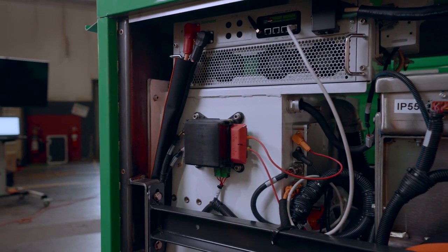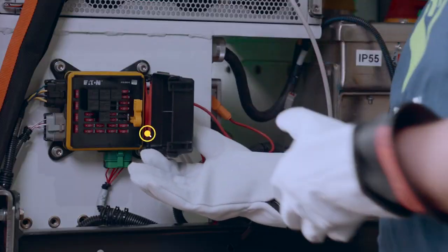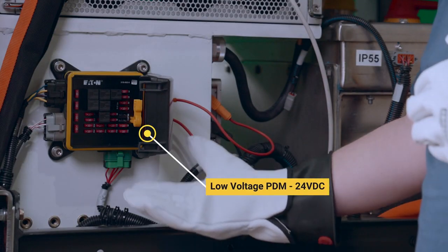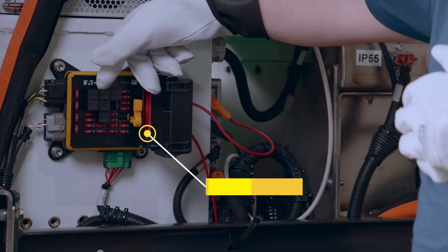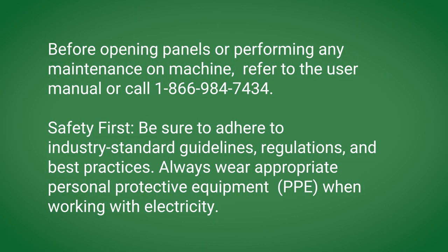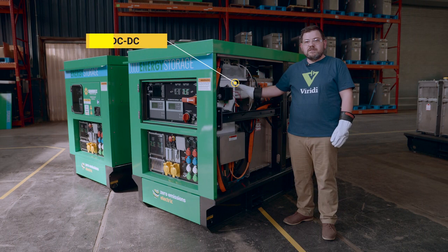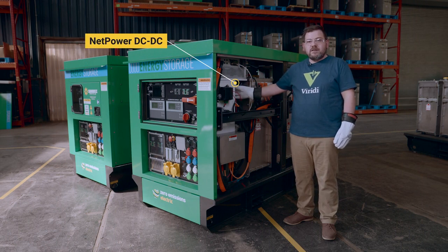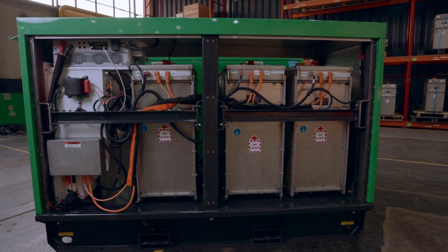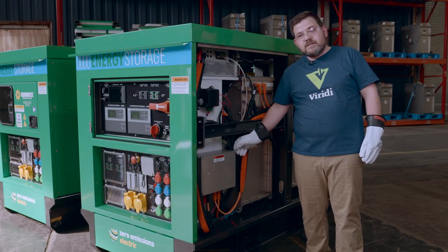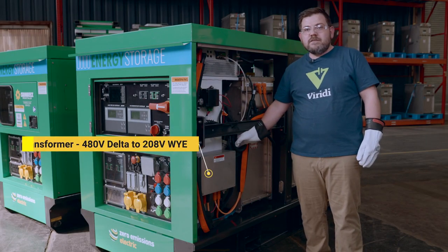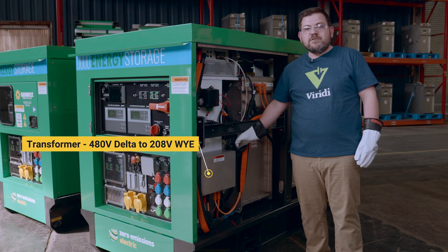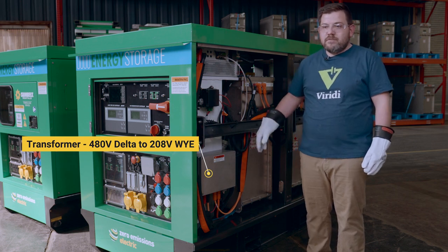Next is our low voltage PDM unit. This is our 24 volt power distribution module, as well as the control module for our 24 volt relays. We have in the back a net power DC-DC, which will help recharge our lead acid batteries that are down below. And buried in here is our transformer that will take our 480 volt delta system and convert it to a 208 volt Y system through our transfer switch.